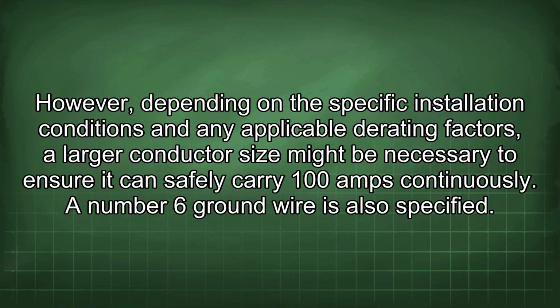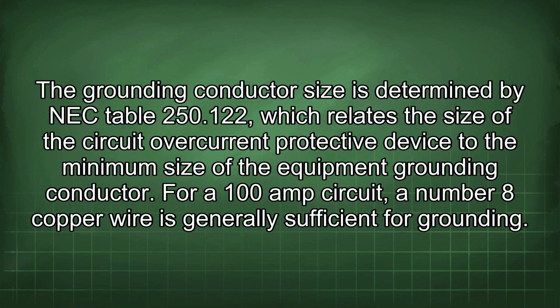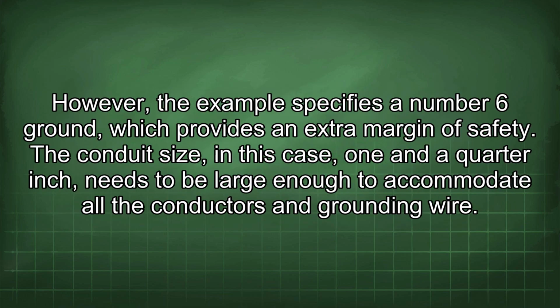A number 6 ground wire is also specified. The grounding conductor size is determined by NEC Table 250.122, which relates the size of the circuit overcurrent protective device to the minimum size of the equipment grounding conductor. For a 100 amp circuit, a number 8 copper wire is generally sufficient for grounding. However, the example specifies a number 6 ground, which provides an extra margin of safety.